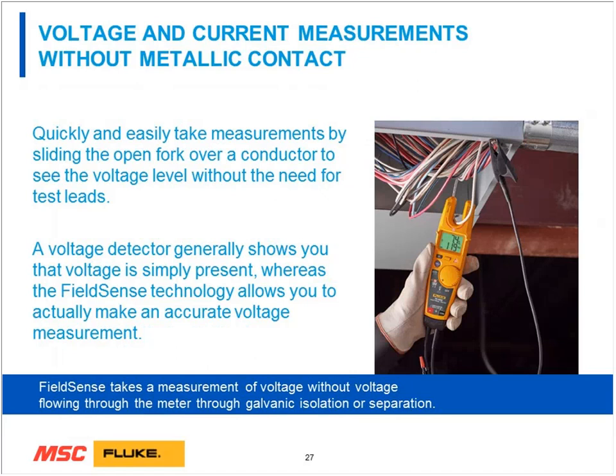Now, we've just recently introduced something brand new to the market. It's called the T6, which doesn't take an active measure, it doesn't make an active contact with a conductor, but it still gives you the ability to measure both current and voltage on the display. So that's something that you may look into. It's something that can keep you away, again, from that active conductor whenever possible.